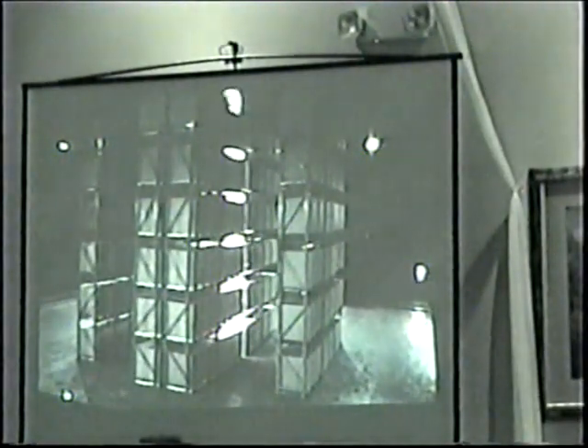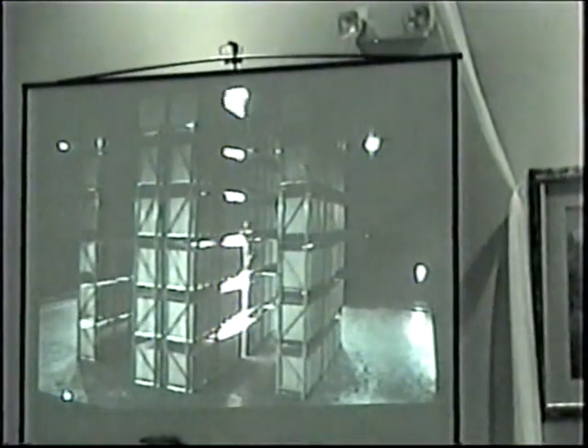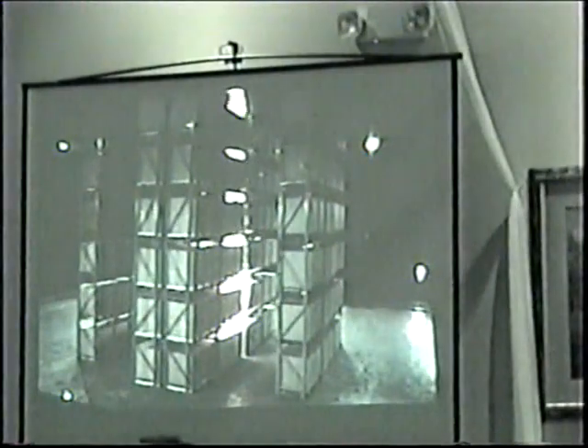These are Ultra K17s. Now this is actually a dry test. So what we'll see, and it's with 286-degree heads, high temperature heads, but it's a dry test, so you'll hear the head go off, and then there'll be a period of delay of about 25 or 30 seconds before the water is actually discharged.